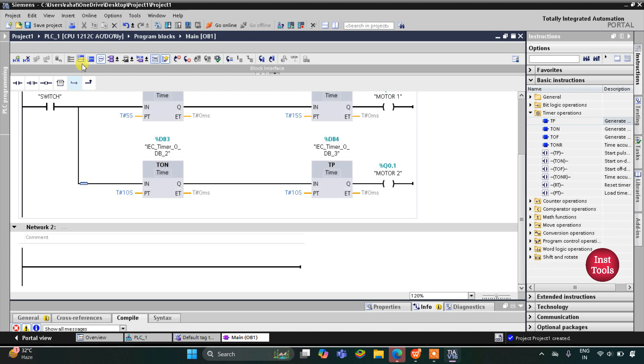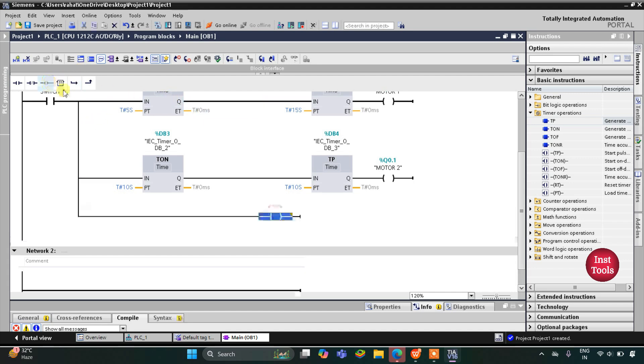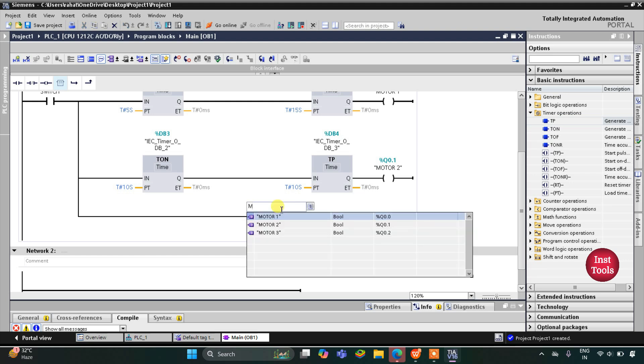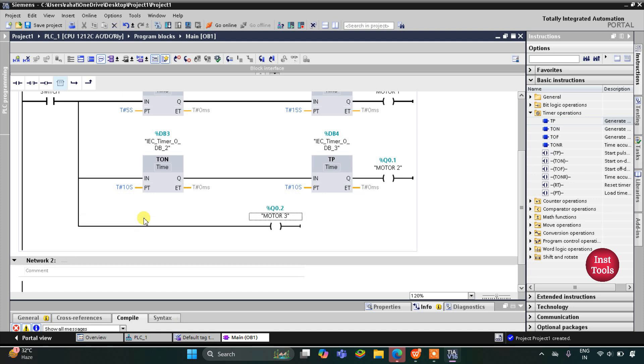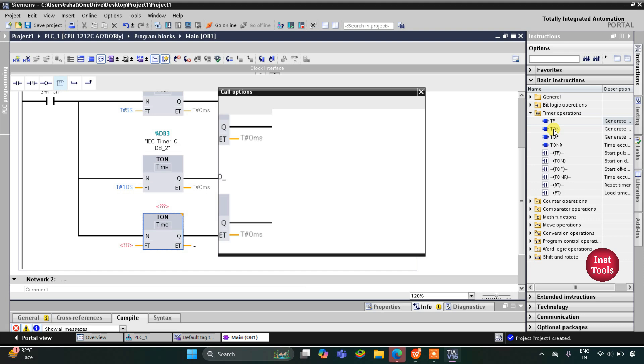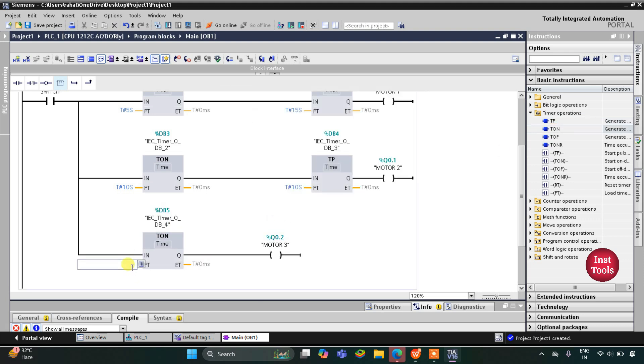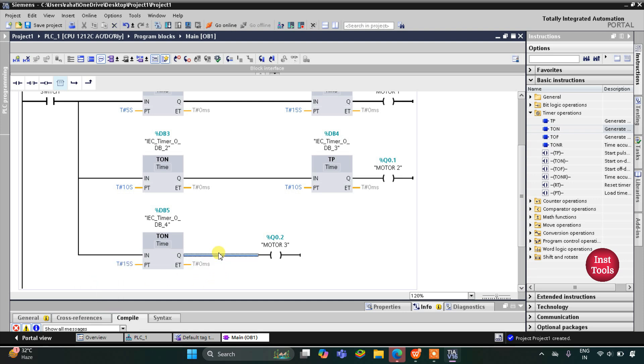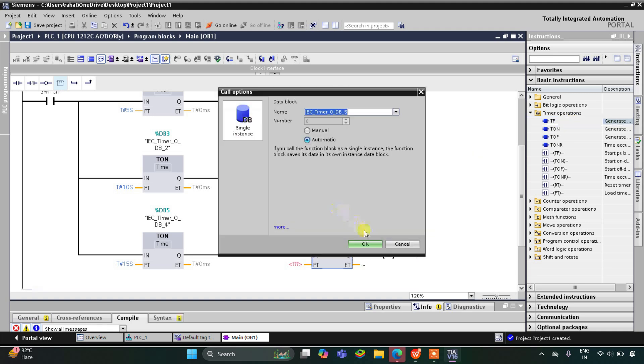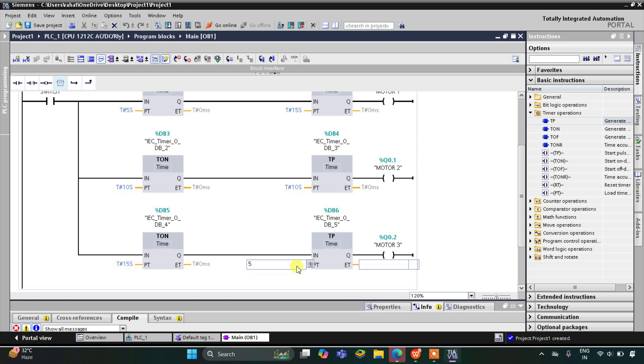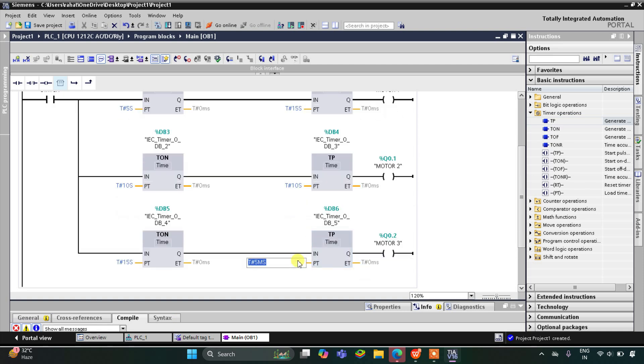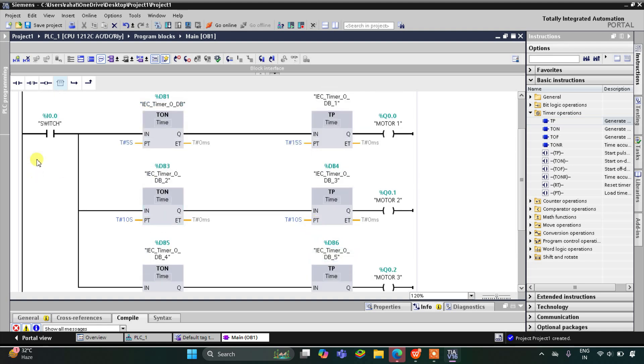After that I will open the branch and insert one more coil for Motor 3. I will write M and select Motor 3. Motor 3 should turn on after 15 seconds, so I will use one more TON timer with a preset value of 15 seconds. Motor 3 should remain on for only 5 seconds, so I will use a Pulse Timer here with a preset value of 5 seconds.